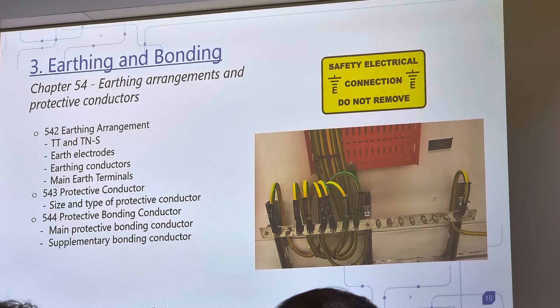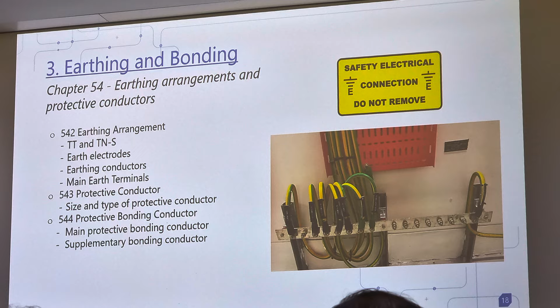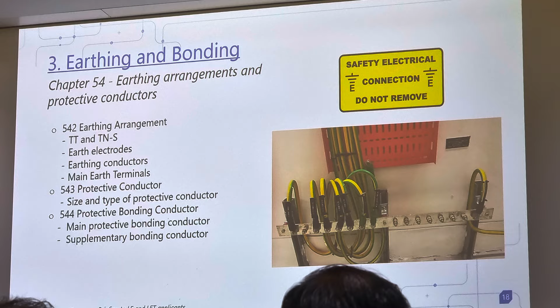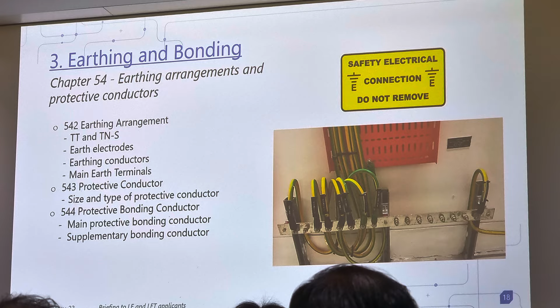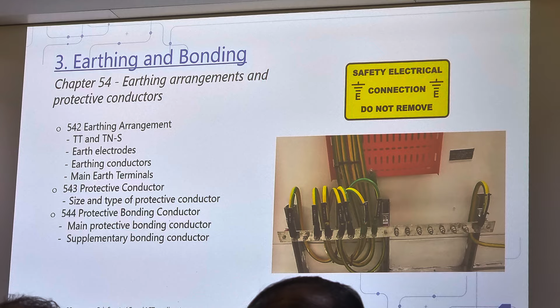Section 543 talks about protective conductors. You must make sure that the protective conductor is able to carry the current it's supposed to carry. When there's a fault, current will flow through the protective conductor. If the conductor is too small, you will not be able to carry the fault current. So as I said about how to size it properly, you don't need to be precise, but you must size it properly so that when there's a fault, it's able to clear it. Some of you may be familiar with some equation. This is the equation that you use. You will not be asked for calculation, but you are expected to know the concept. What does this equation mean? What is K? What is S?